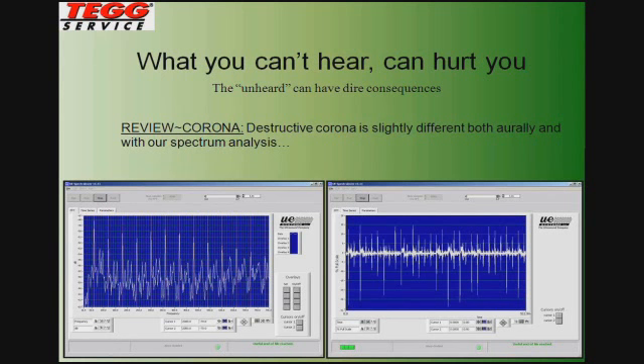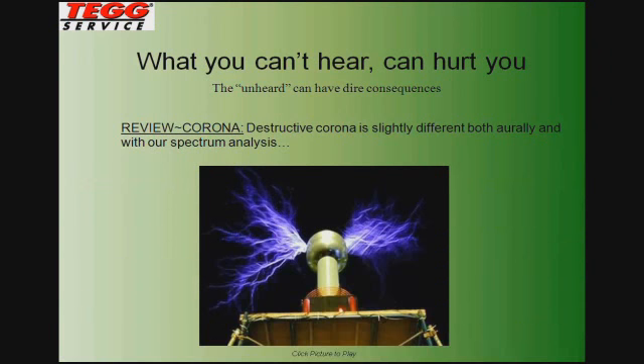The destructive corona. I mentioned nuisance corona, and we just looked at the spectrums for that. Where destructive corona comes in, this naturally occurring process of ionization will ultimately release nitrates into the air. And when those nitrates mix with the moisture in the air, it forms a nitric acid. And nitric acid degrades and destroys electrical insulators. When this destruction occurs, you begin to have discharges of electricity along those insulators, i.e. tracking.